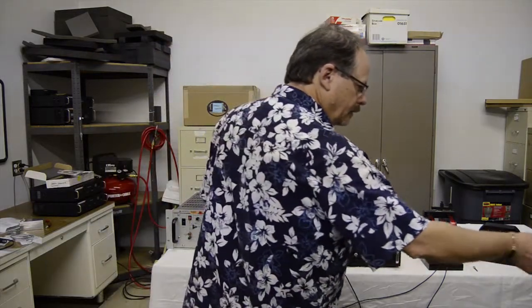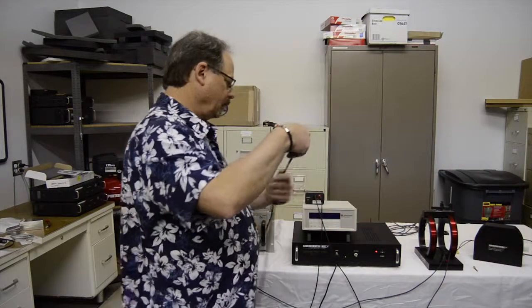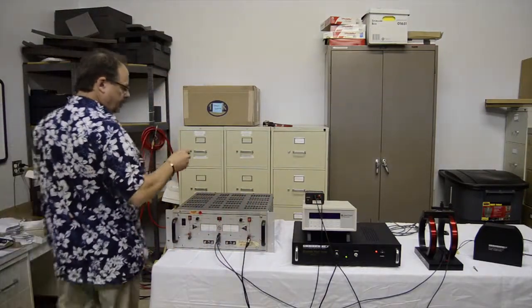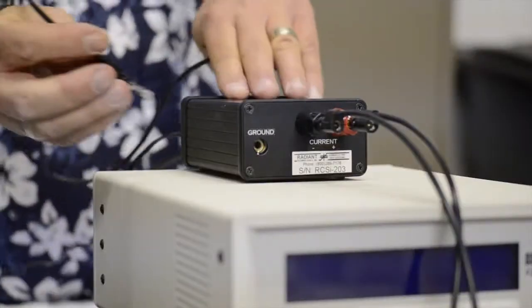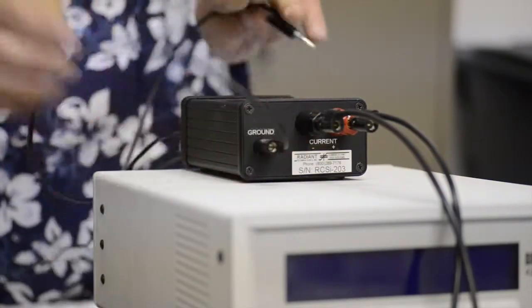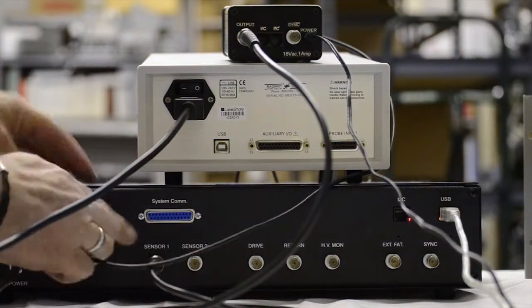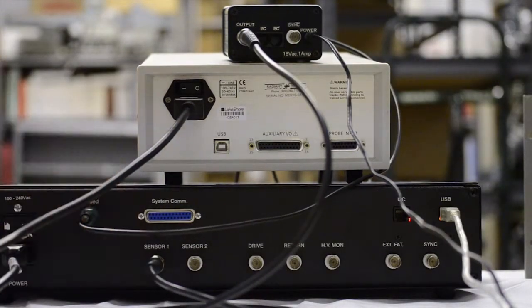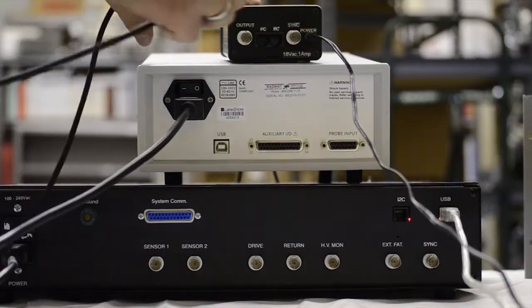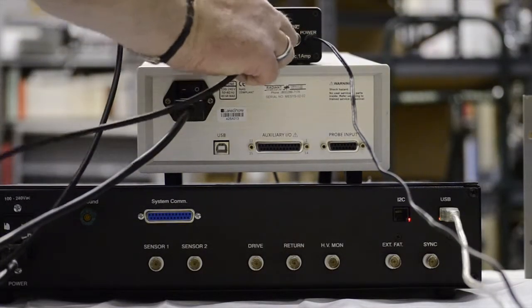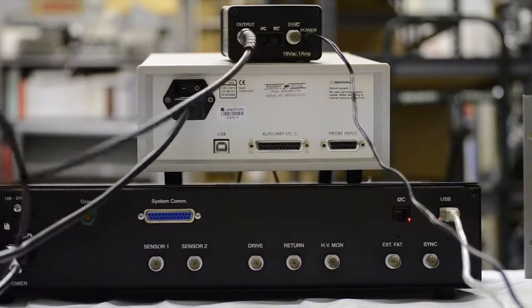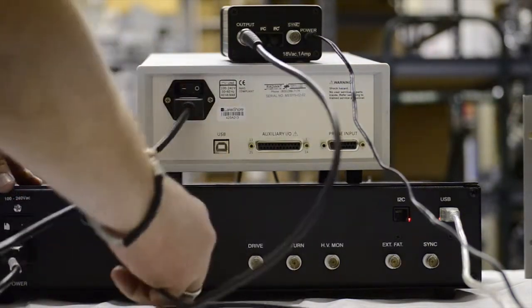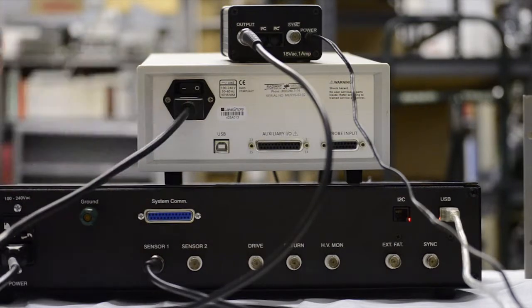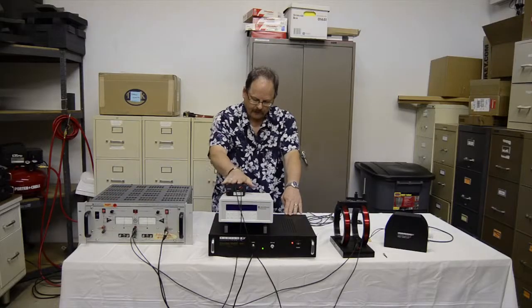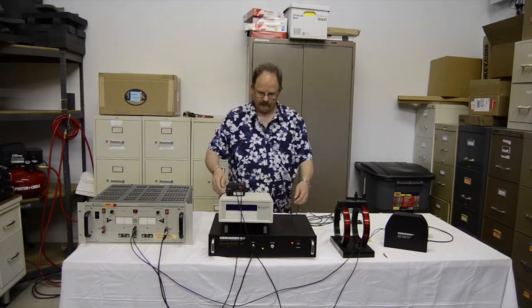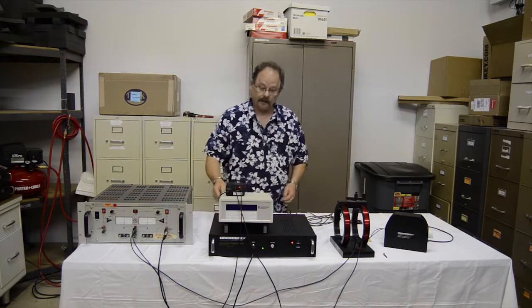At the rear panel, I'm going to first connect the ground plug of the current sensor into the green ground plug of the tester. Then we take the output of the current sensor, and not the sync port, the output port, into the sensor 1 port of the tester. And that completes the configuration of the current signal path.